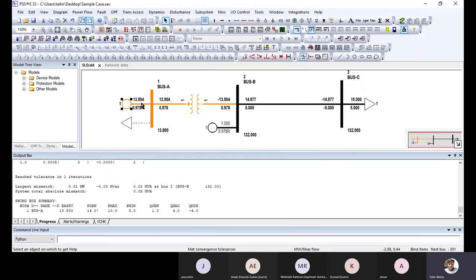It will supply 13, but it will give you an error here, an asterisk, saying that P max is 10 megawatt. You need to add another 4 megawatt generator. Okay. Yes. So basically, this is how you control the system.